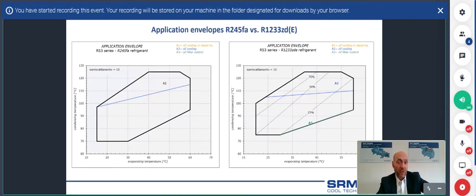In terms of application envelope, these are the application envelopes of the compressors for both refrigerants, which are quite similar in terms of condensing temperature. They both can run up to 125 degrees C for this compressor series. While in terms of evaporating temperature, the 245 can be used also at 15 degrees C, while for the 1233 the minimum evaporating temperature is actually 20 degrees C.